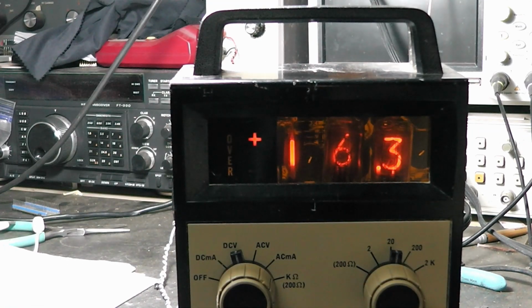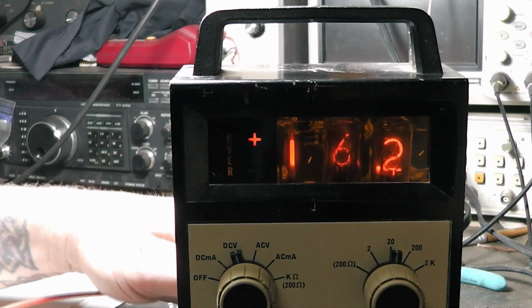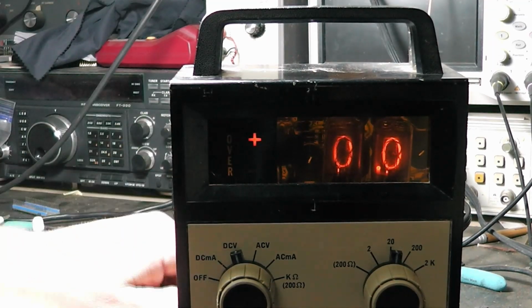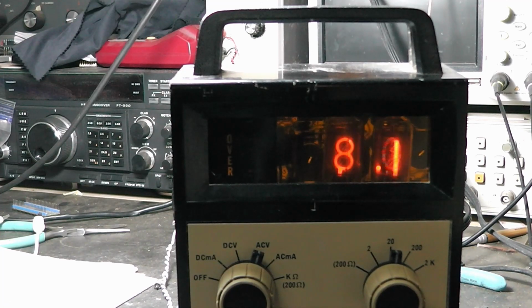It says note the reading may vary a little bit, but gets close to 16.3. A proper adjustment will read out 16.3 most of the time. So try to get it at 16.3. Remove the probe from the AC cal test point and turn the function switch to the AC volts position. So we'll take that off. Put this to the AC volts position. And it's going to take a second to settle when you do that. It always does on these things, just the way the 74 series logic chips are doing their timing and counting in there.